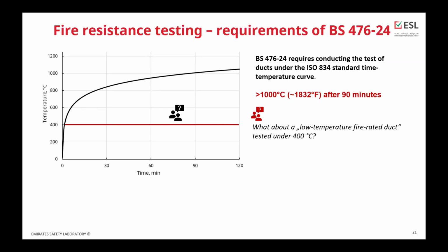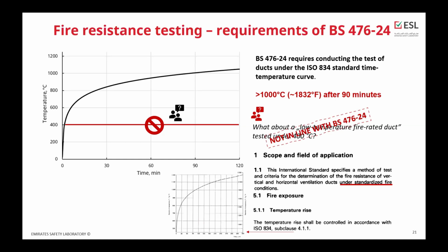I had several questions regarding the low temperature fire rated ducts, which are tested under 400 degrees. Is it possible? Is it allowed, or maybe not appropriate, or maybe not in line with the standard? So it's not really in line with the standard, and this is why: the scope of BS 476 part 24 is horizontal and vertical ducts, which are tested under standardized fire conditions, which are referred to ISO 834. So based on BS 476 part 24, it's not in line.